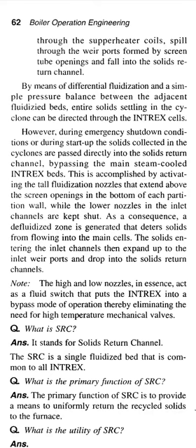As a consequence, a defluidization zone is generated that deters solids from flowing into the main cell. The solids entering the inlet channels then expand up to the inlet weir ports and drop into the solid return channels. Note: the high and low nozzles in essence act as a fluid switch that puts the Intrex into a bypass mode of operation, thereby eliminating the need for high temperature mechanical valves.